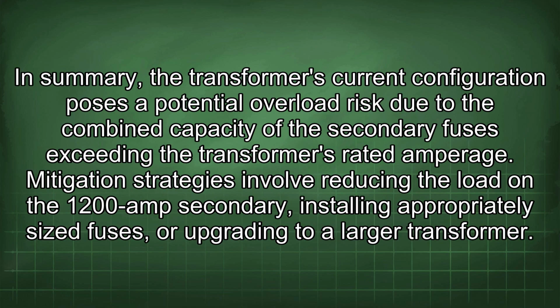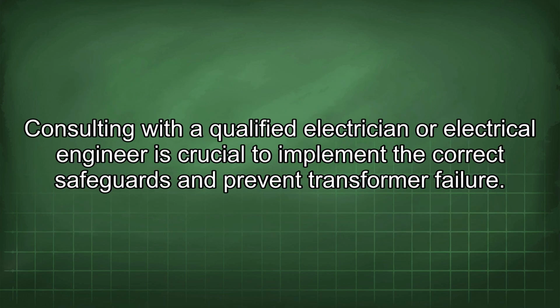In summary, the transformer's current configuration poses a potential overload risk due to the combined capacity of the secondary fuses exceeding the transformer's rated amperage. Mitigation strategies involve reducing the load on the 1200 amp secondary, installing appropriately sized fuses, or upgrading to a larger transformer. Consulting with a qualified electrician or electrical engineer is crucial to implement the correct safeguards and prevent transformer failure.